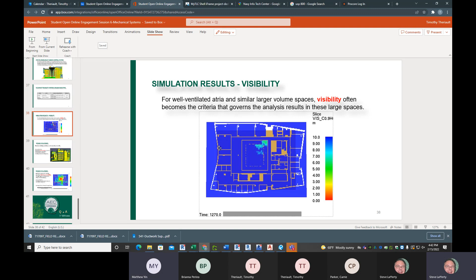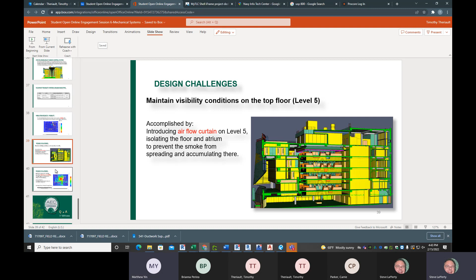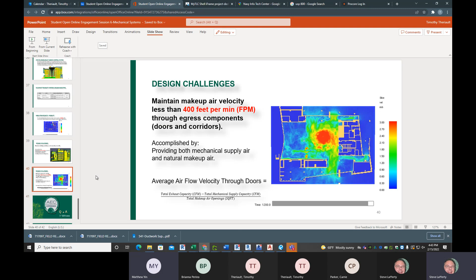That's a design challenge. So as Tim mentioned, we employ a pink slot vent for blowing air - that's the air curtain to separate the smoke from the atrium. Next slide, this is the visibility. This is the velocity of the air coming through the openings, which we need to maintain lower than 400 feet per minute. All the green means air coming in, and the red is hot gas and smoke. You see a little bit of turbulence in the center of the building. Going further, entering the building, that green is fresh air. So that's the smoke control system we designed.